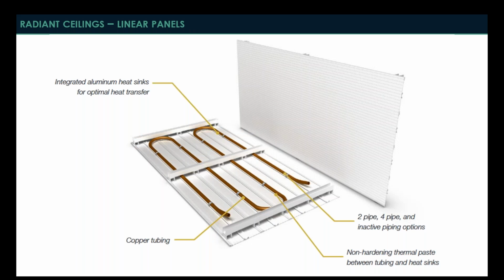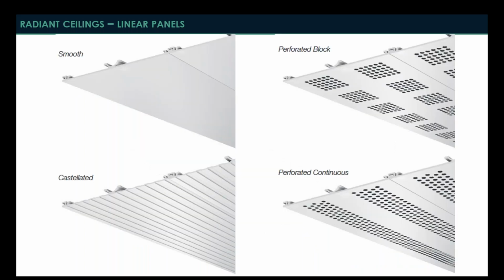Another type of radiant ceiling panel is what we call linear panels. Now, these are very similar to the modular type. The real difference being that it's just an extruded aluminum or steel shape, and the idea is that they are very linear. You can have very long runs of these seamlessly connected together for a very clean look. The way that the energy transfer works for the linear panel is almost identical to how the modular panel works. You have the copper tubing essentially attached to the backside of the aluminum panel itself.